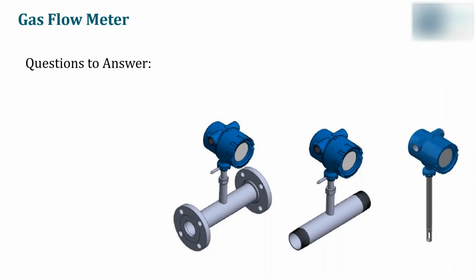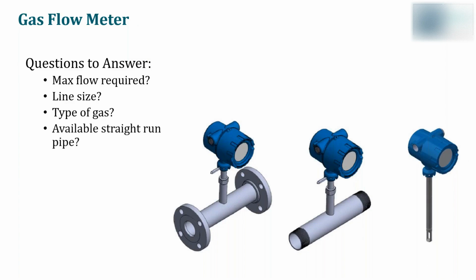Now, gas flow meter. Questions that need to be answered is, what is the max flow that is required? What is the current line size? What type of gas is it? What is the available straight run pipe? Now, straight run pipe is very important because with these meters, they normally require 15 pipe diameters upstream and 10 pipe diameters downstream.